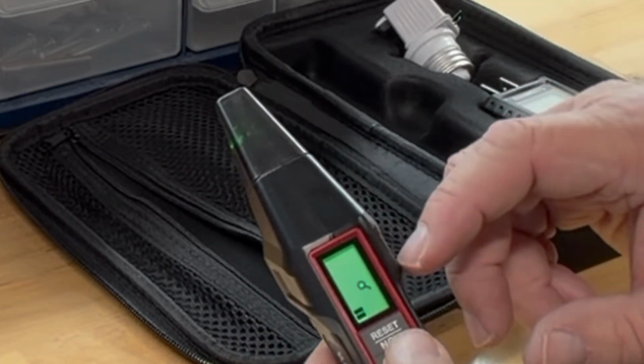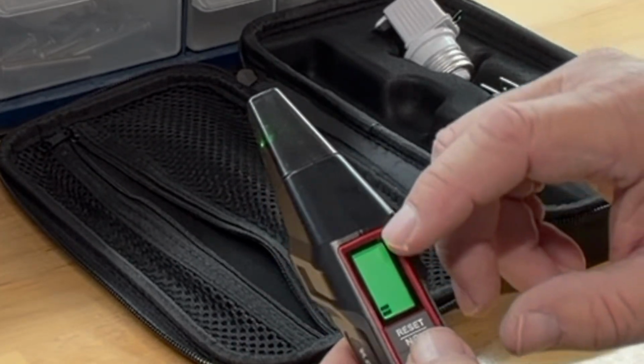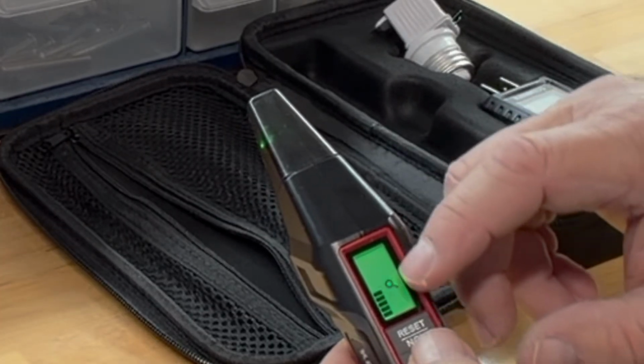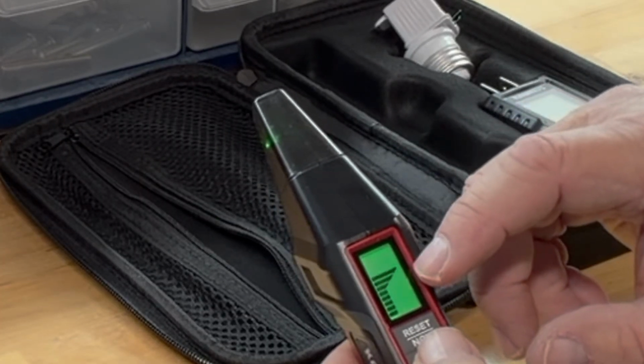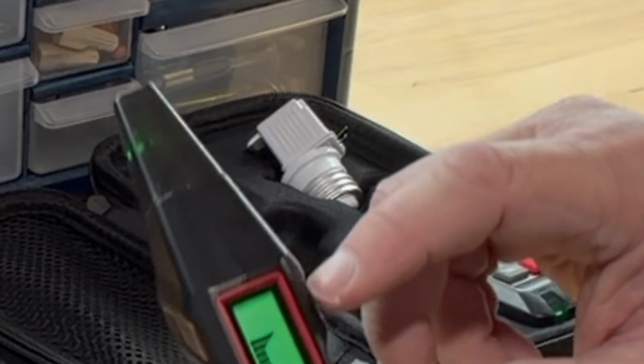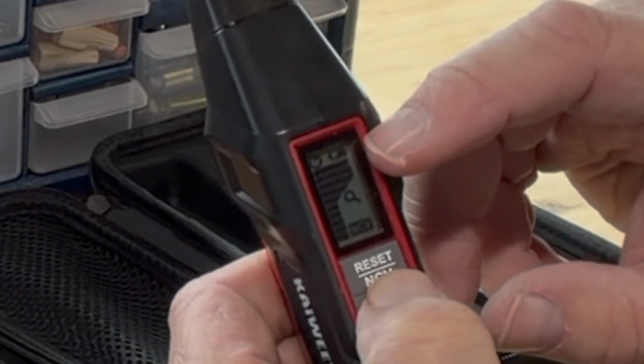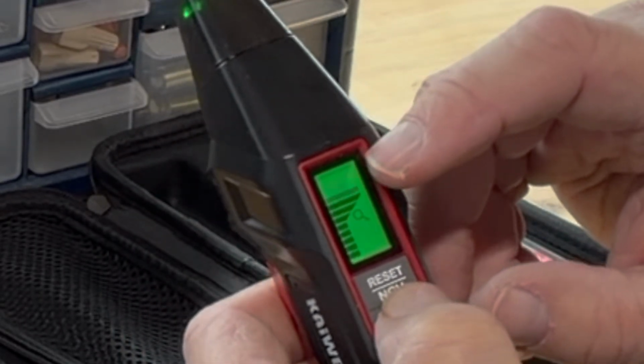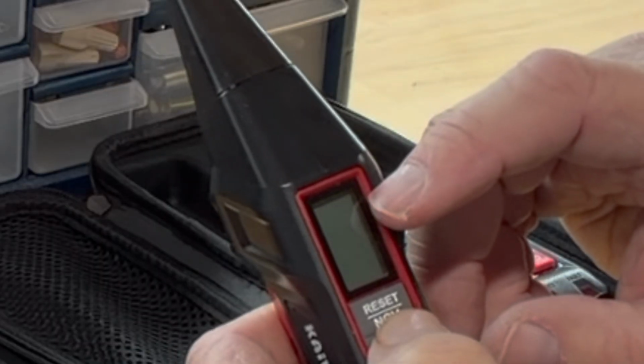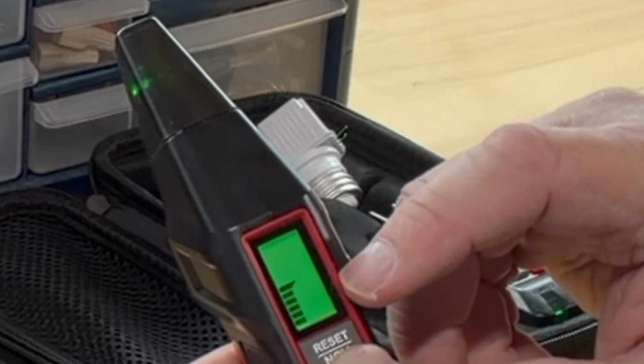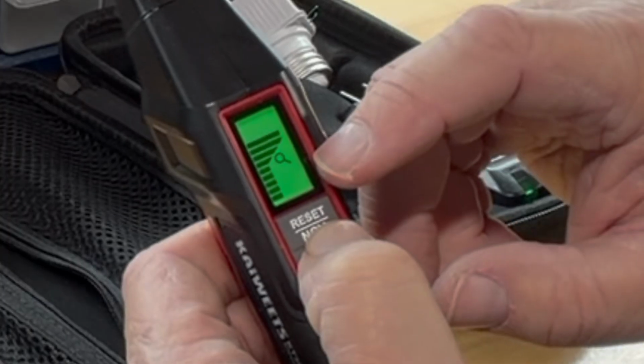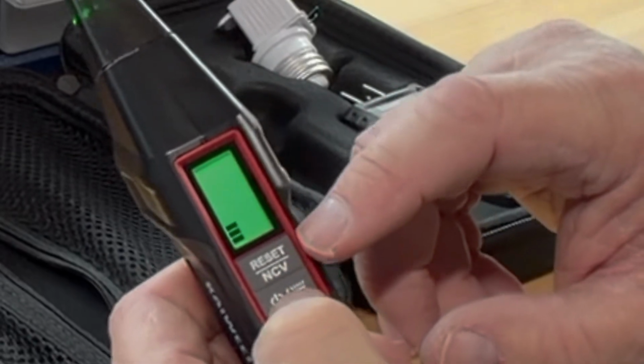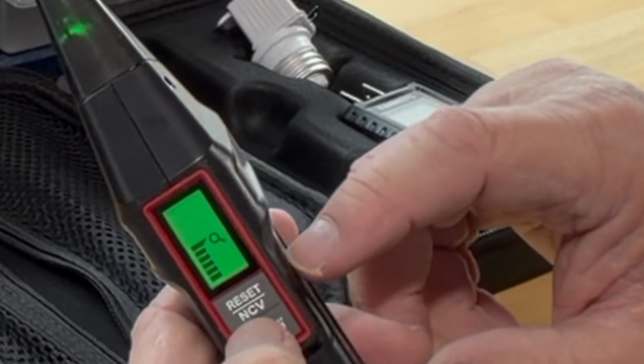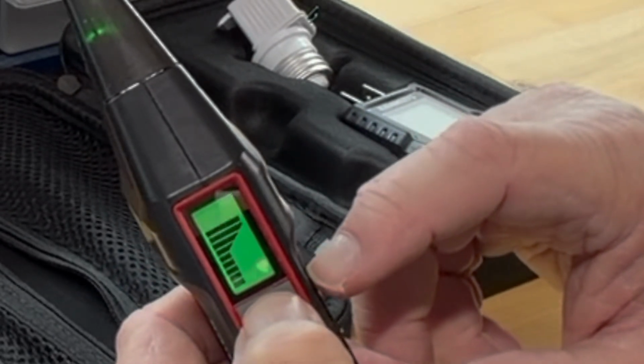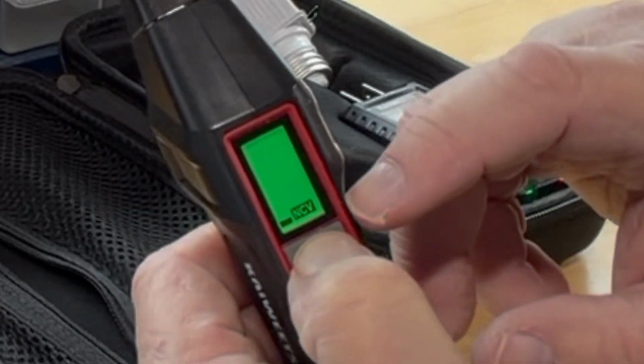You can see when you turn it on, you see the signal strength bar. It's going up, full strength. Also, when you first turn it on, up here at the upper right, you can see the battery indicator. It flashes by so fast, you can't see it. And then there's a little magnifying glass. It's a lookup mode. And then if you hold this button down, it says NCV, no contact volts. Hold it down and switch it to that mode.